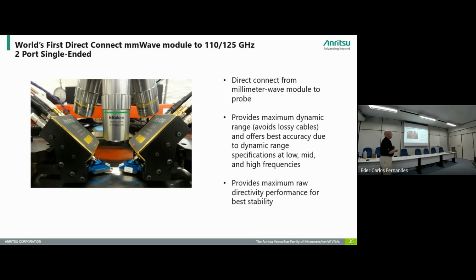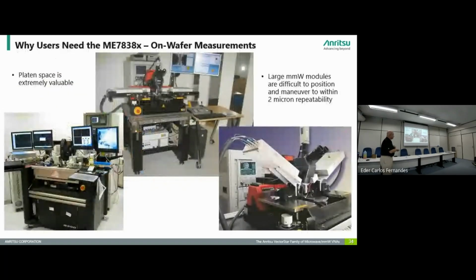Plus, we're getting better raw directivity because we're bringing everything closer to the probe. A lot of these older systems, like these here, actually had negative directivity, which is a terrible thing because you had long cables back to the coupler, and so that created negative directivity, which, if your raw directivity is bad, no matter how well you correct it, it's still going to drift over time and temperature.